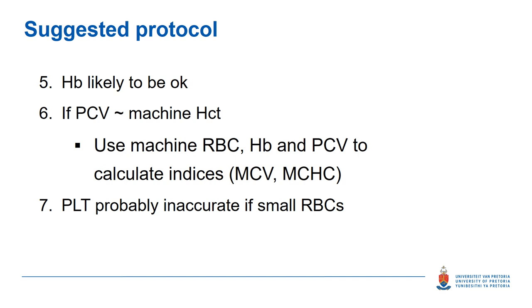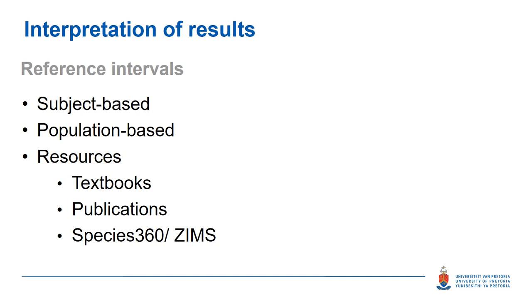If you have a species with very small red cells, be aware that your platelet count may be inaccurate because the analyzer cannot differentiate well between platelets and small red cells; you will need to examine the smear and do a subjective evaluation of platelet numbers. The white blood cell count is usually reasonably consistent and we generally don't see wide variations in white cell count depending on species setting. Once you've gathered results, you need to interpret them, and this is another big problem area because we do not have reference intervals for most species.